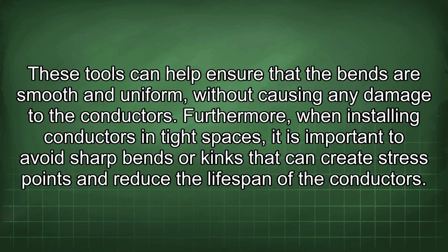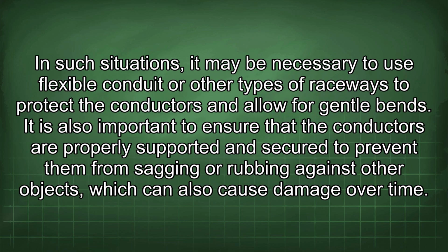Furthermore, when installing conductors in tight spaces, it is important to avoid sharp bends or kinks that can create stress points and reduce the lifespan of the conductors. In such situations, it may be necessary to use flexible conduit or other types of raceways to protect the conductors and allow for gentle bends. It is also important to ensure that the conductors are properly supported and secured to prevent them from sagging or rubbing against other objects, which can also cause damage over time.